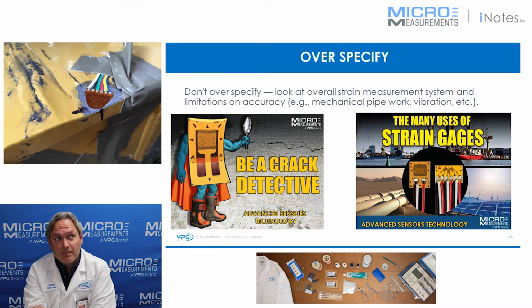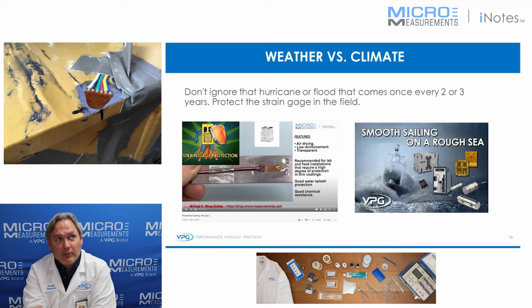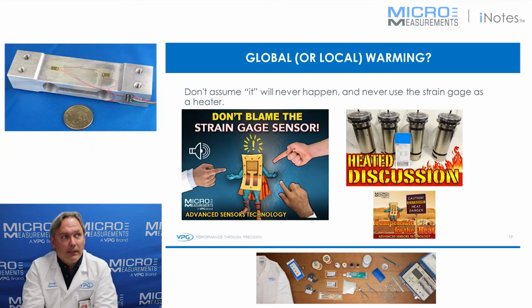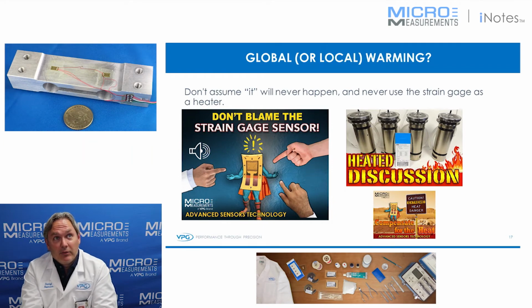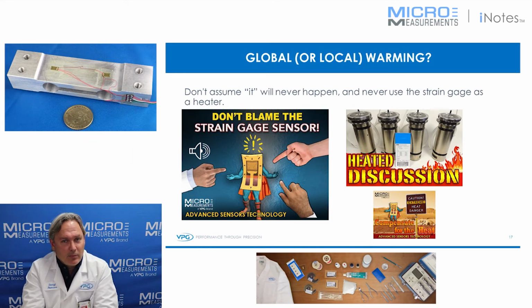Don't overspecify. Look at the overall strain measurement system and limitations on accuracy, such as mechanical pipework, vibration, but look at the entire system. Think of the strain gauge as just one piece of a much broader, larger system. And don't assume it will never happen, and never use the strain gauge as a heater. Just like we were talking about a few minutes ago, in order to determine the right excitation level, we're trying to avoid a phenomenon called self-heating, where you put too much power into it and it starts to warm up and it creates a drift, and we don't want that in our measurements.